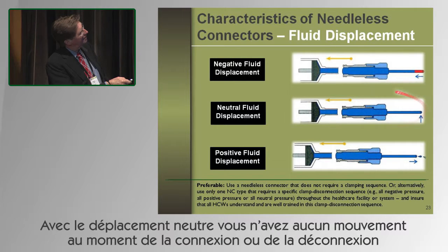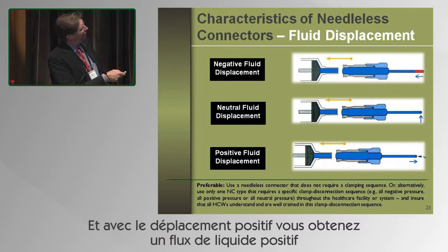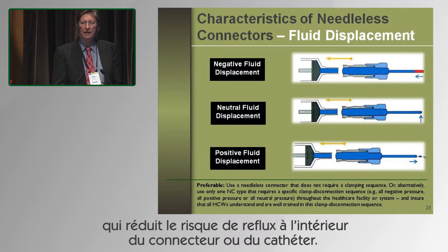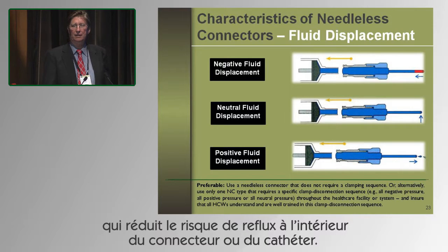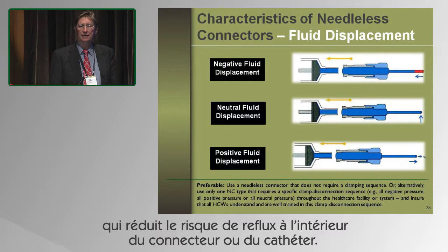With neutral displacement, with disconnect or connect, you get no movement either out or in. And with positive fluid displacement, you initially get positive flow with disconnection, and it reduces the risk of reverse flow or negative flow into the connector or the catheter.